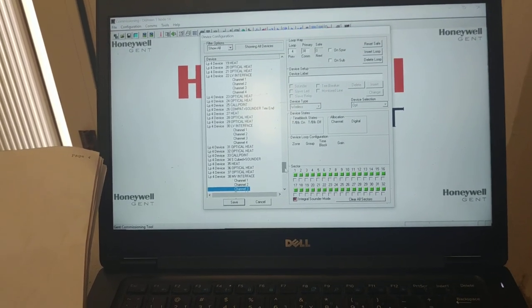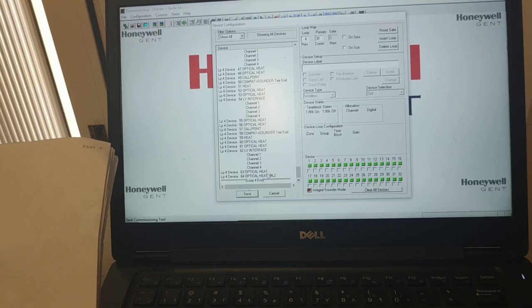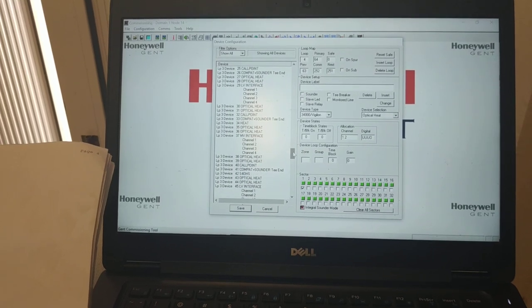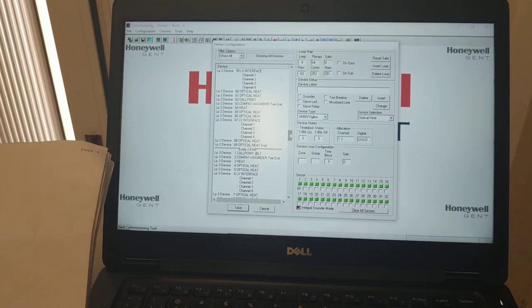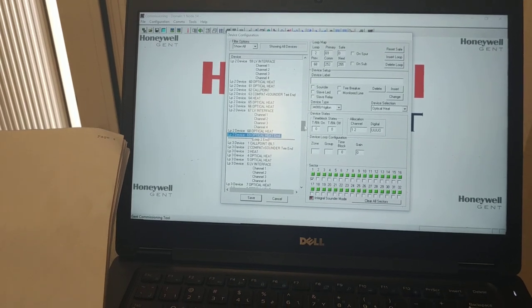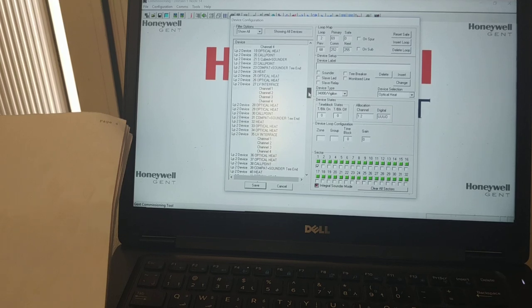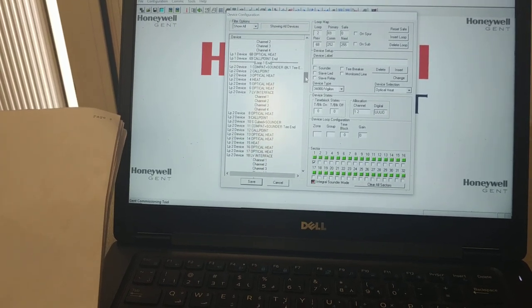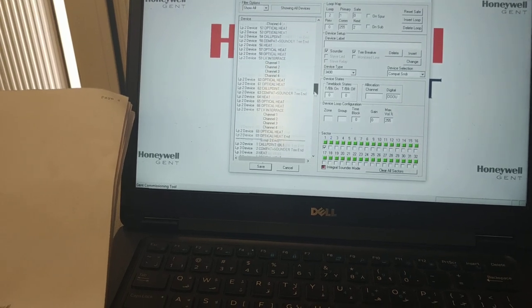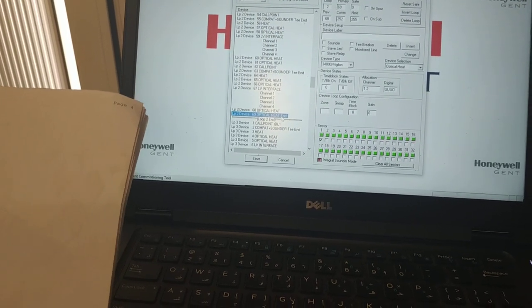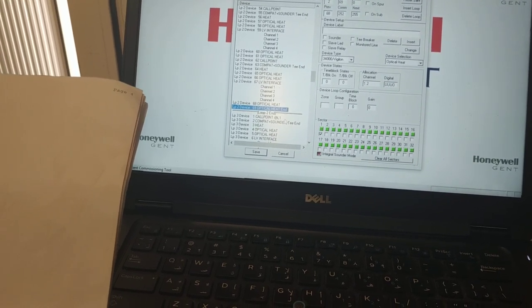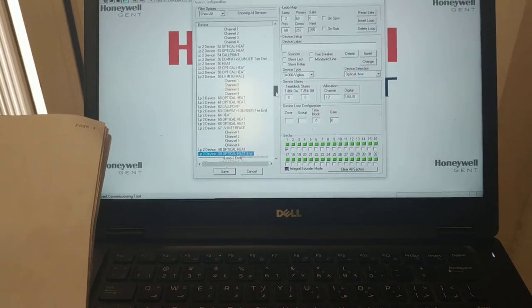How many devices each? It's 64. This is L2 — complete. Loop 2 is 69. Let me check if it is split or not. This is Line 1, Line 2 — Loop 2 is split. Only 69 devices. For this, I think there are some minimal device bypasses here. From 1 to 69 it's okay, so 72 to 85 is bypassed.